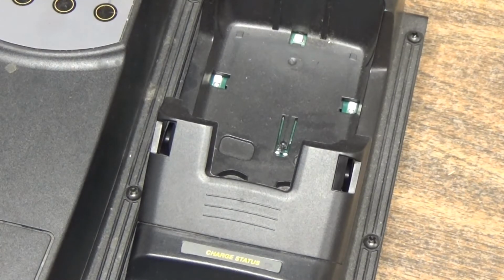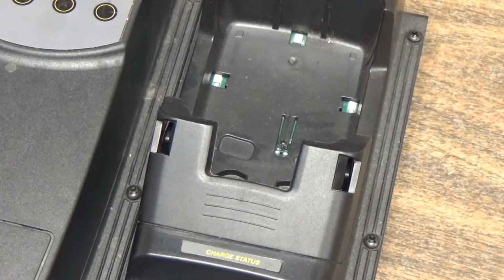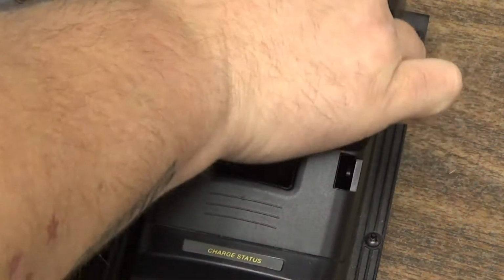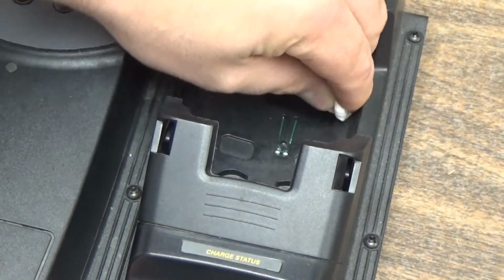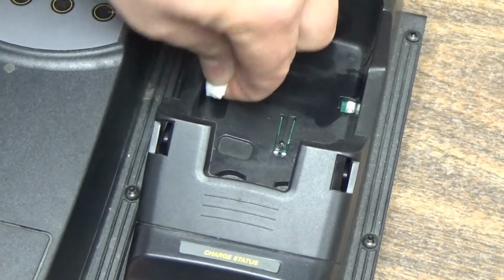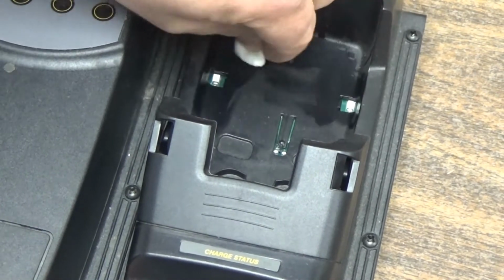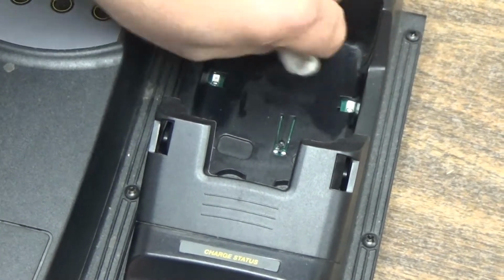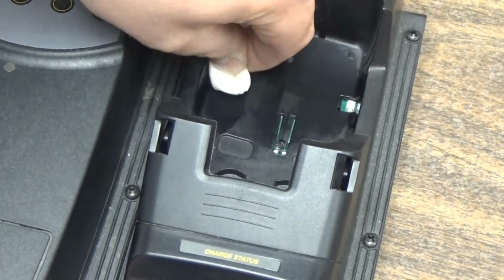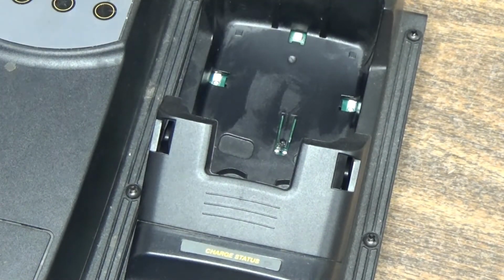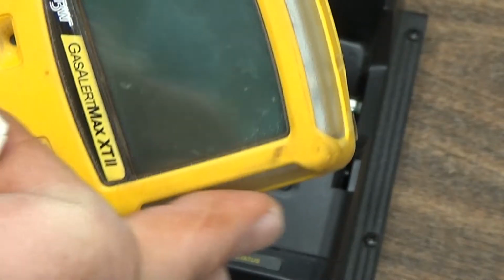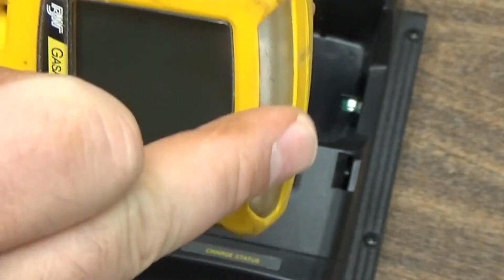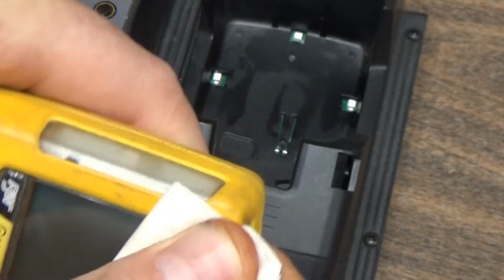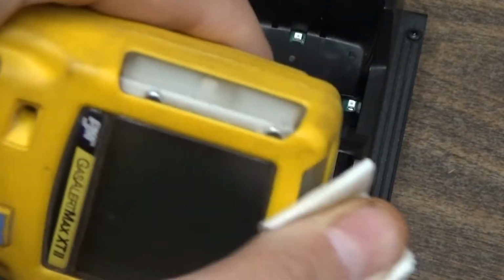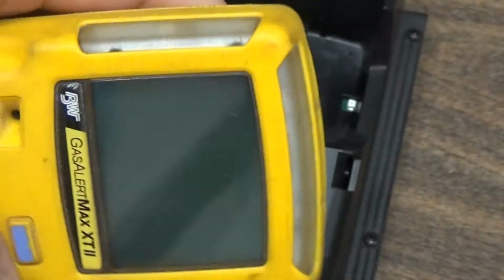white checks that read that alarm on the meter. Just kind of wipe them off. Let it air dry for just a couple minutes. After you wipe them off, that gets all the dirt and dust off of the sensor. And then also on the meter, around the outside edges where that bump station reads the flashing lights, go ahead and clean those and make sure that that bump station can read those flashing lights, and also let it air dry for a few minutes.